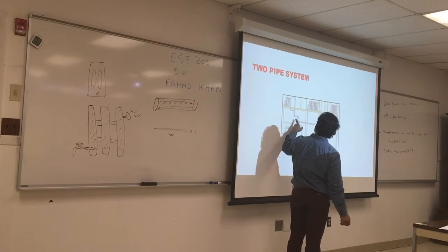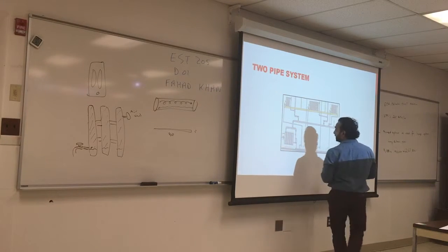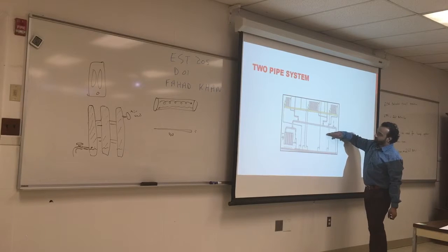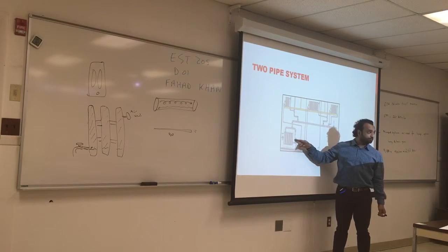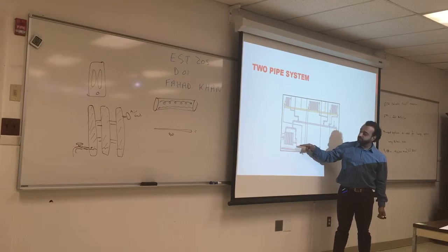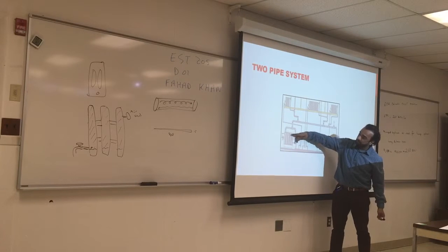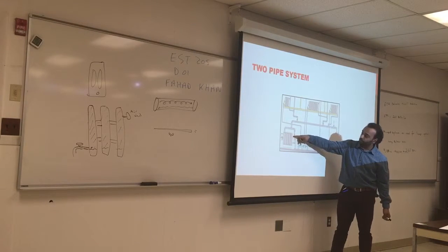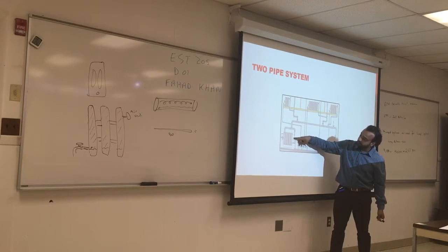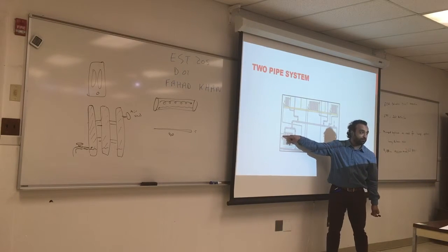The condensate of the water will gather in these pipes, and usually we'll have water all the way to the top here, and this is the Hartford loop that maintains the water in that system. The water can go up and down in the system, but it should not exceed the level of the top of the boiler. This is the sight glass that you always look at. The water level here is the same as in the boiler, and the same as here in the Hartford loop.